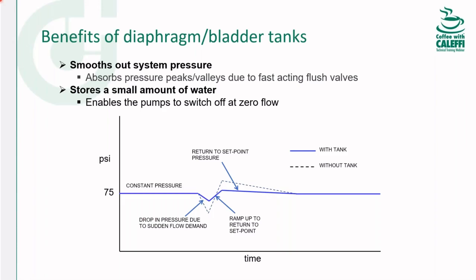And then we've got another reason to use diaphragm tanks with booster systems. I think low flow shutdown is probably the most important reason to use a diaphragm or bladder tank today in modern pressure boosters, if this system will encounter low flow situations. This allows for a very efficient pump stoppage during these low flow periods. So it's key to have the diaphragm tank for low flow stoppage. And that's an energy code requirement today also, and we'll probably talk about that later. Yeah.